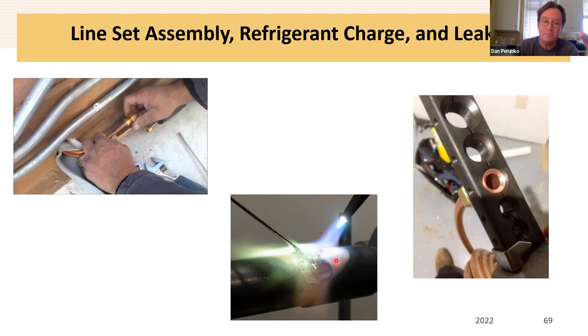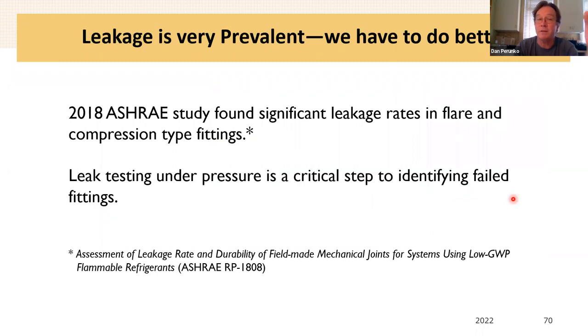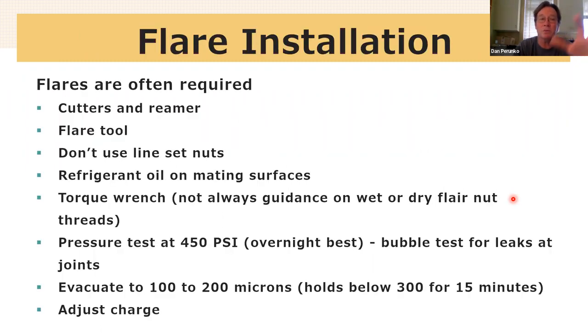The legacy systems are brazed, which is this process, and brazing is a little easier to do without causing a leak than flaring is, but most of the new systems require flares, so we have to get good at this. This is an ASHRAE study. They're an engineering organization, and they were studying how good flares are, and they basically came to the conclusion that flares leak, that it was very hard to do flares that don't leak. And I don't think it's a great study. It doesn't have a large enough sample size, but the conclusion is something that I think might not be inaccurate. It's very hard to make these things so they don't leak, so we have to be really careful.